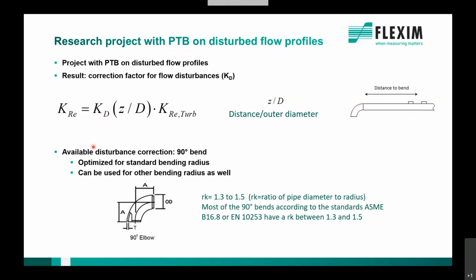So at the moment, FLEXIM introduced that one for the 90-degree bend. That was the first disturbance we were able to implement. Other disturbances will follow in the near future. 90-degree bends have different bending radii. If you look into the standard, there is an ASME standard B16.8 and a European standard for it. It defines that most bending radii are between 1.3 and 1.5. So that's defined, and that's the optimized correction factor for those bending radii.